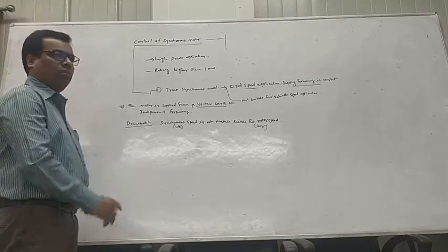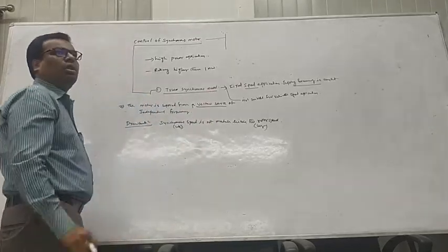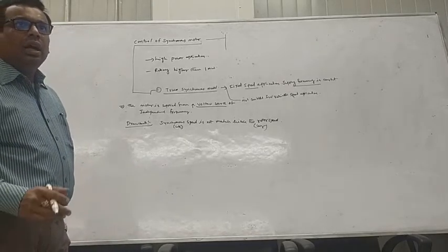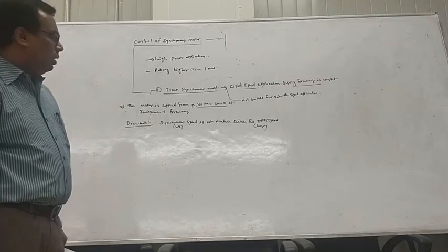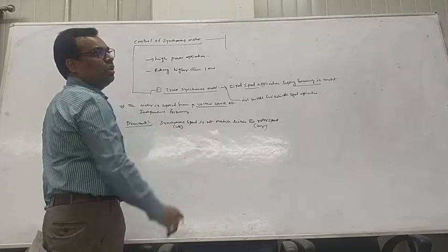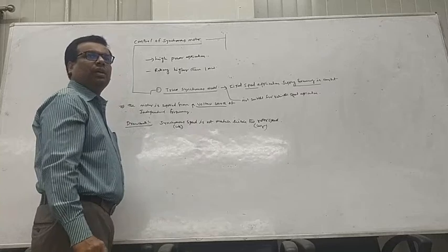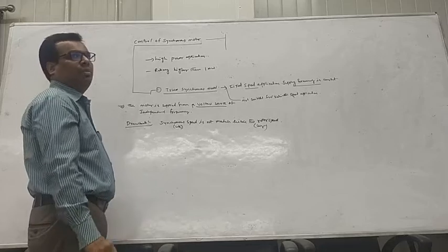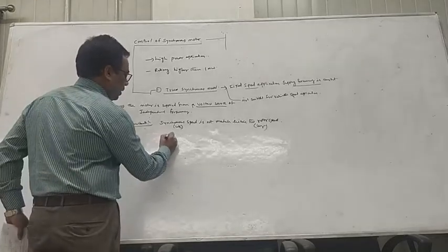So the main problem with respect to the true synchronous mode is that the true synchronous motor is supplied from a voltage source of an independent frequency. And this is not suitable for variable speed applications. In fixed speed applications, your synchronous speed is not matched with the rotor speed. Whenever this happens, definitely there will be some vibrations, and those vibrations are called the hunting phenomenon, and this will cause the hunting problem.